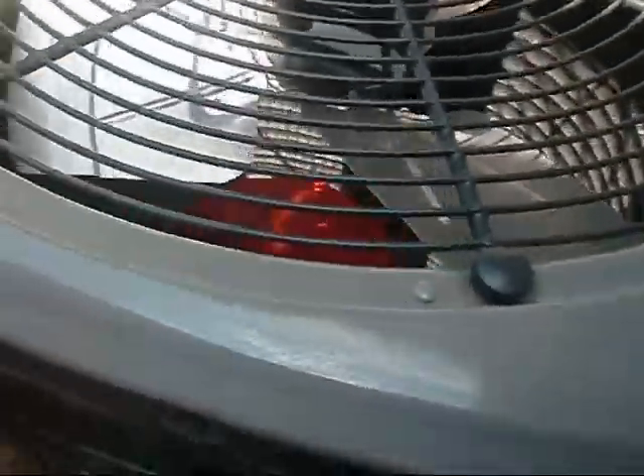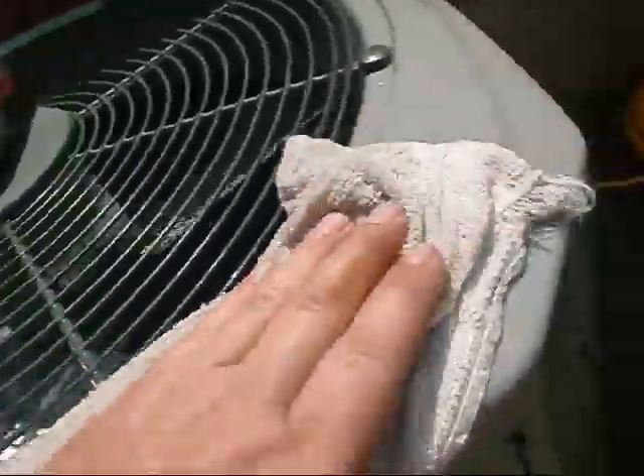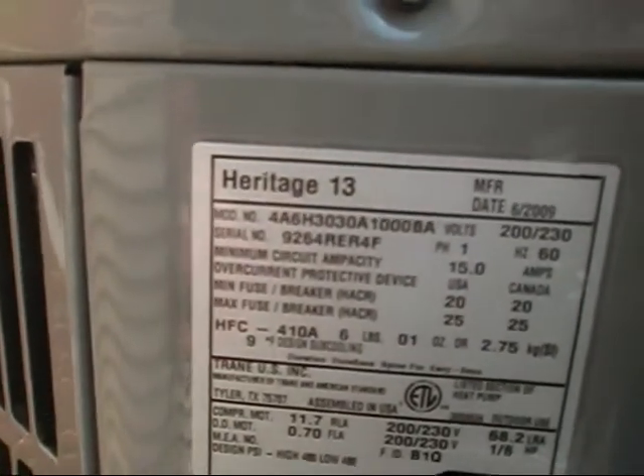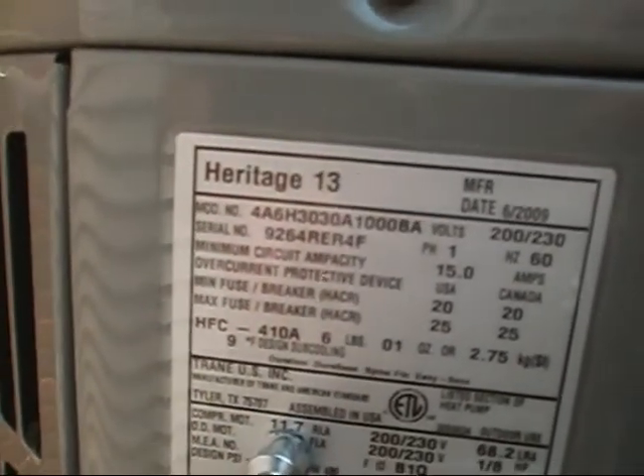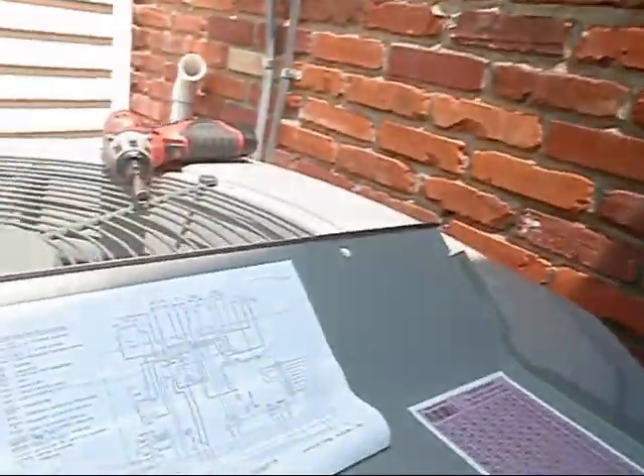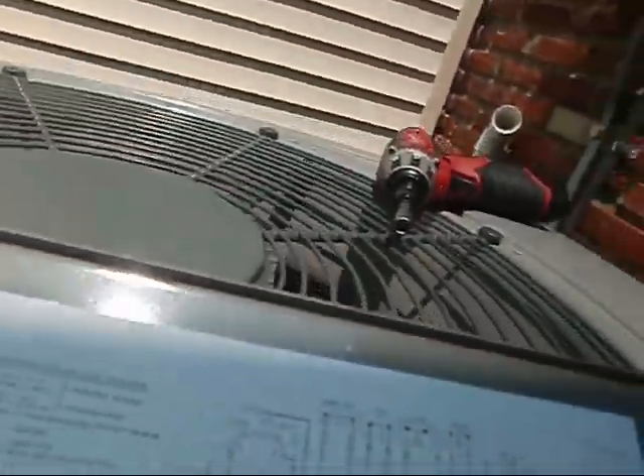I know it seems redundant, guys, but that's just the way I roll — and this is before you even slap the gauges on her. Compressor motor: 11.7 RLA — rated load amps. So let's go over here to our little schematic, look for our common wire, which is right here. It looks like it's the black wire, BKBL. I need my glasses, but that's what it is. It looks like it's going right here to T2, coming off the common on the compressor.